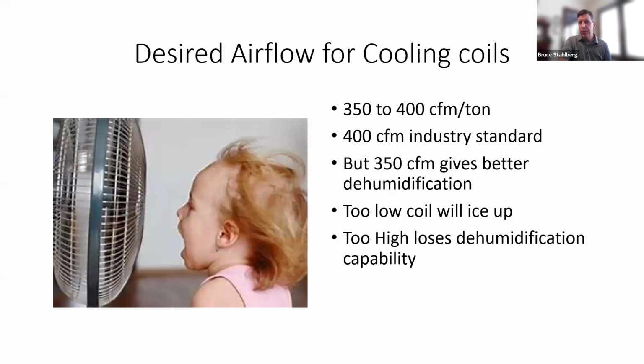Desired airflow for cooling coils is 350 to 400 CFM per ton. So remember, the sizing comes into play. If that's a 2-ton unit, we're looking at 700 to 800 CFM. In the past, 400 CFM has been kind of an industry standard. But the closer we get to 350 gives us better dehumidification, which is really what we're trying to do with air conditioning. We're trying to dry the air out. So there are different ratings for the coils that you can get into a deeper dive on this. But if we go too low, we can freeze the coil. If we go too high, we lose dehumidification capability.